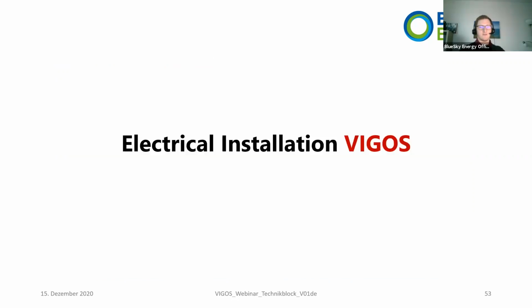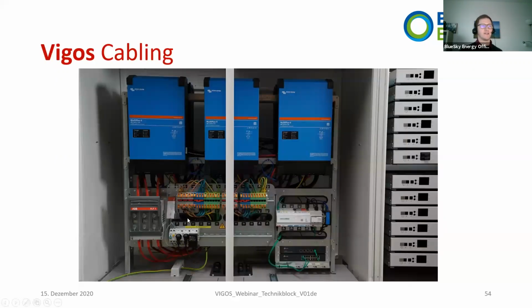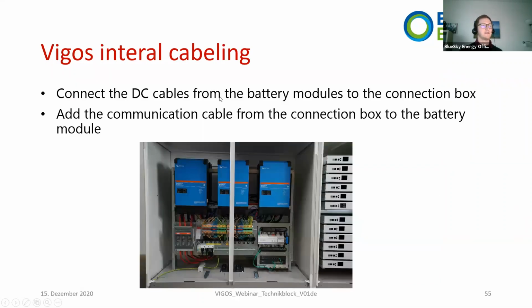Good, so now we go directly to the electrical installation of the Vigos itself. First we'll go through the cabling, which you can see inside here. The whole connection box is already pre-cabled, so pre-wired, and you just need to add your AC cabling, your energy meter cabling, and what you also need to do is install the DC cables from the battery modules to the connection box. On the bottom here, I hope you can see these small gaps. You can break out this sheet also on this side, and then you will have cables which you can connect from the bottom of the housing to the other side. This is the whole DC connections you have to do for plus and minus. And also one communication cable needs to be connected from the connection box to the battery module.